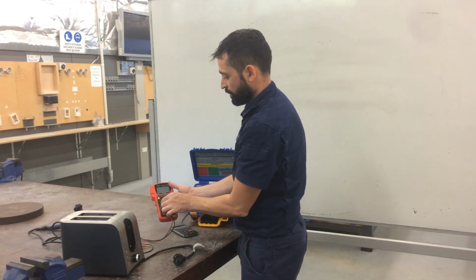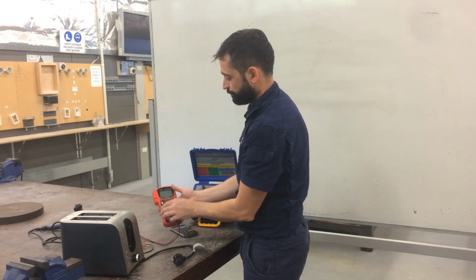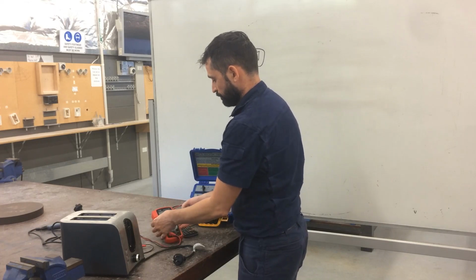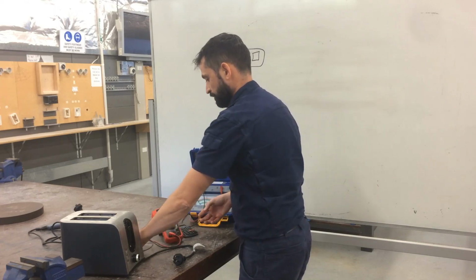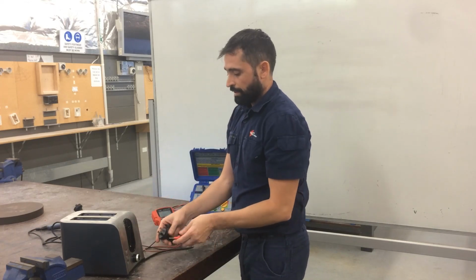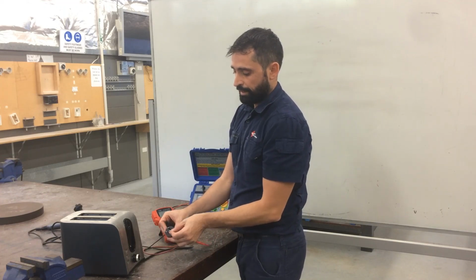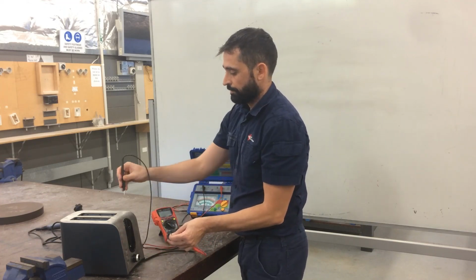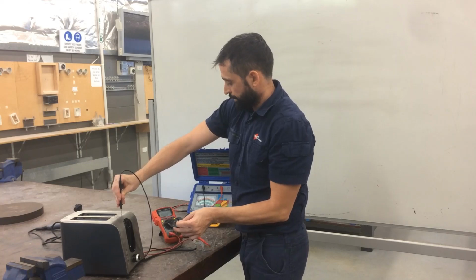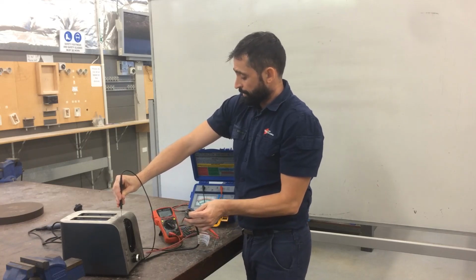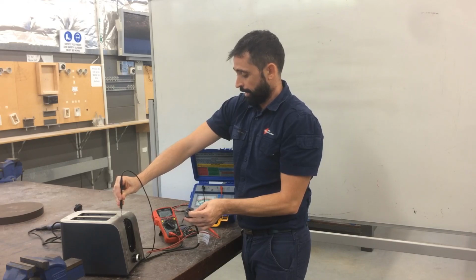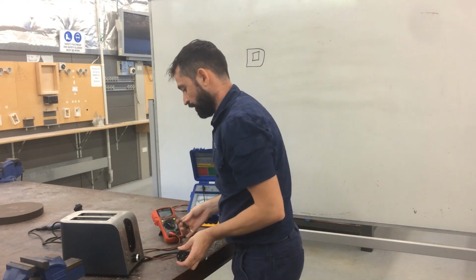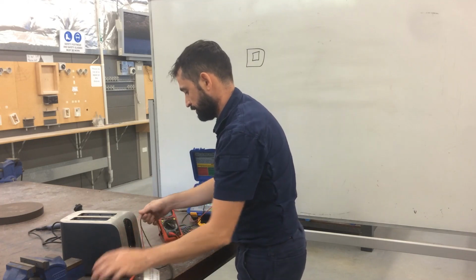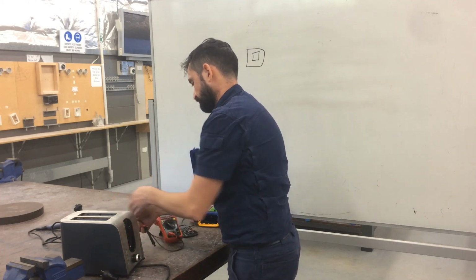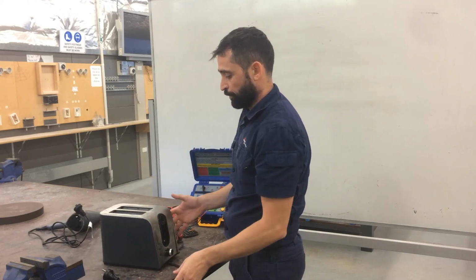So we're going to get a digital multimeter, and we're going to set it on the ohms range. I'll put one of our probes against the earth terminal and the other on any conductive part that you see. I'm getting 0.0 ohms. So that's excellent continuity, and we can move on to the next test, which is the insulation resistance test.